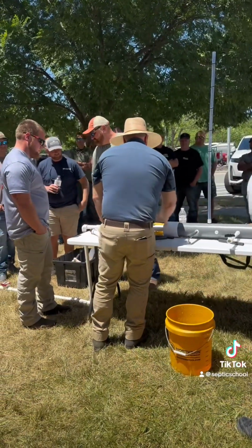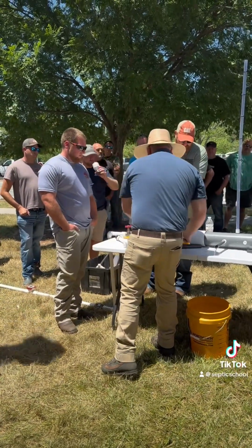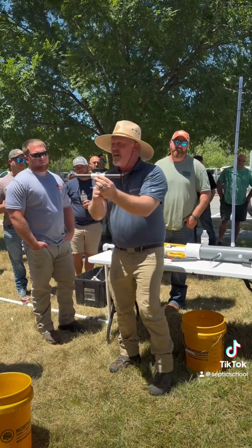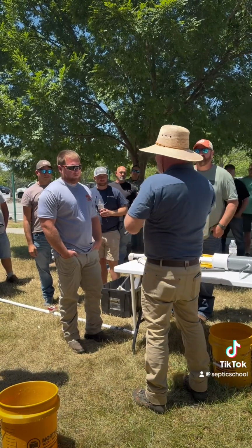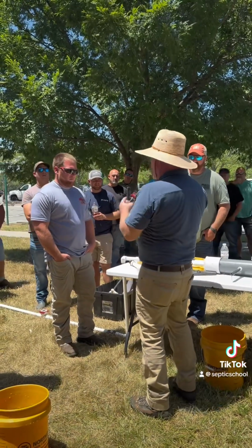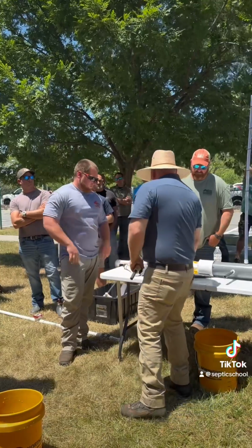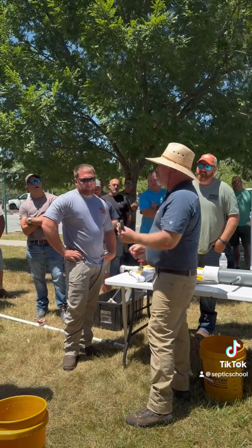I've got counties that were actually making me do something else. I had counties that would see something like this and they would panic. They would panic because I got Schedule 80, and then this valve they found out is not a full port valve. What does full port mean? The guts inside the valve are a slight restriction. This valve is a full port valve. And so they said, man, if you're going to use that, that's a restriction. They said, not only that, dadgummit, we're going to take the valve out of the equation. We want you to, when you're using a 1/2 inch pipe, go up to a 3/4 inch valve.